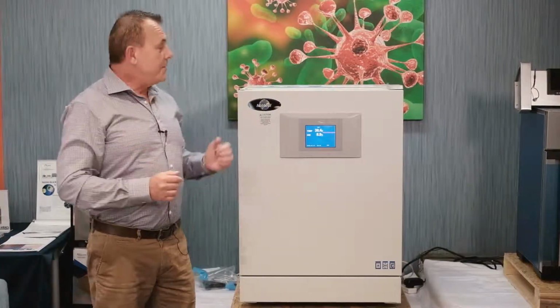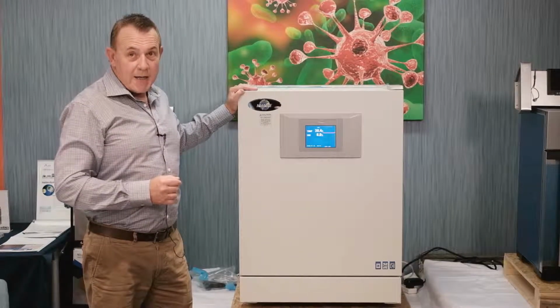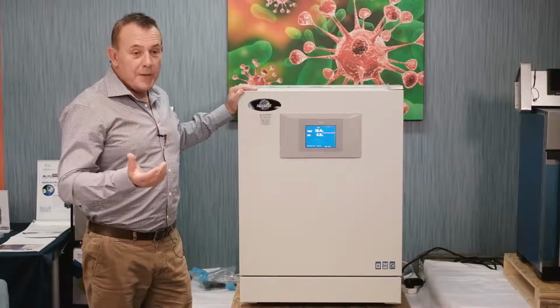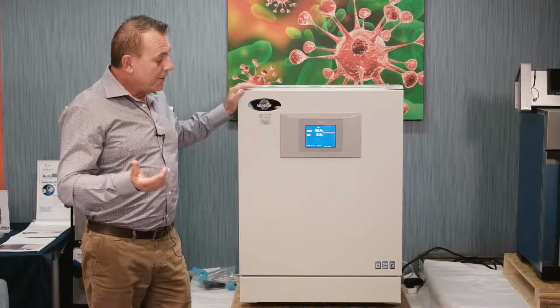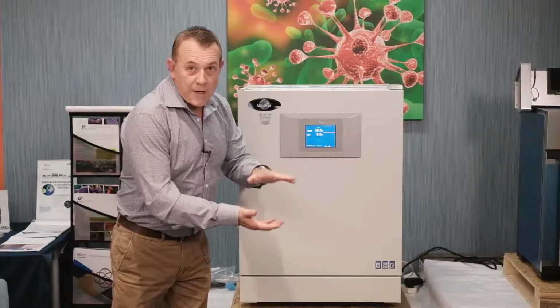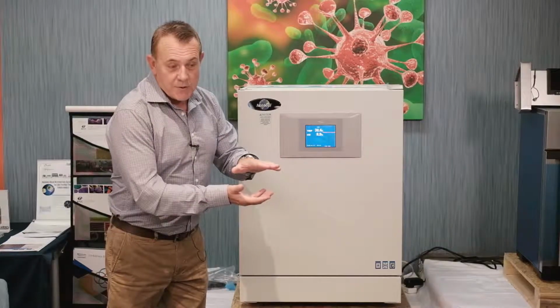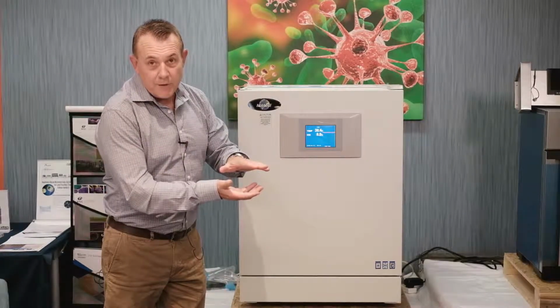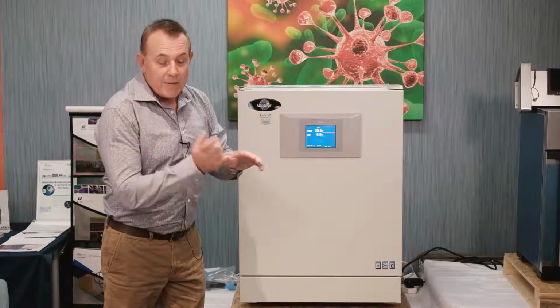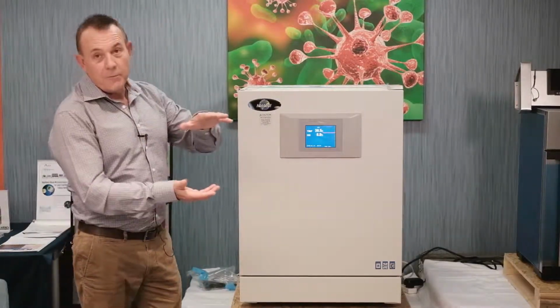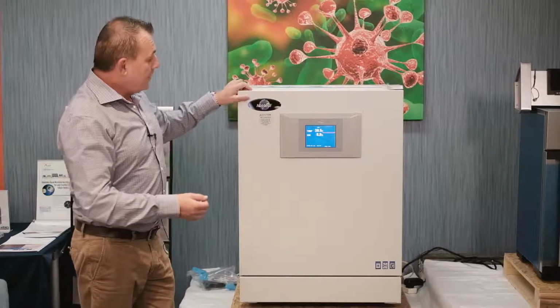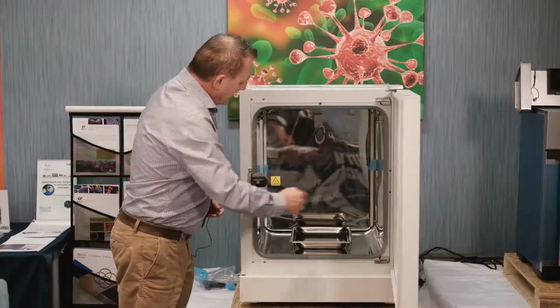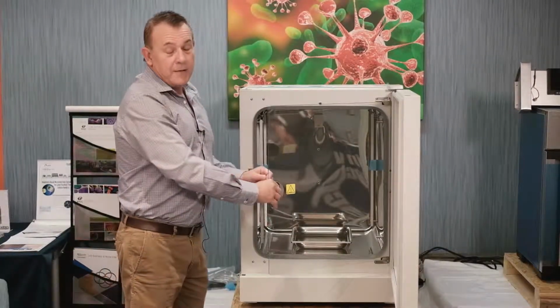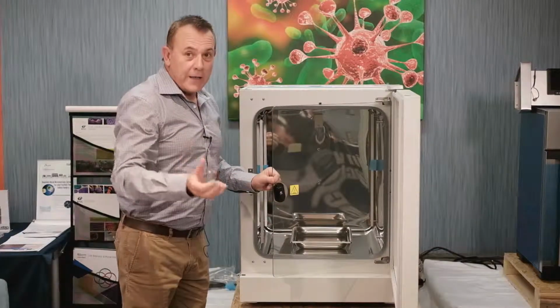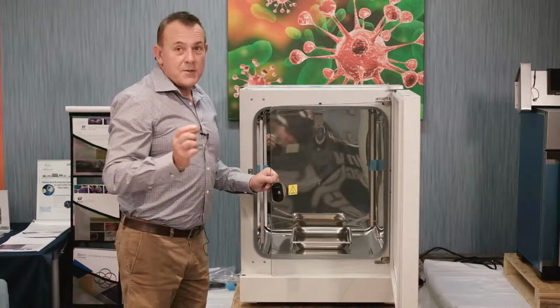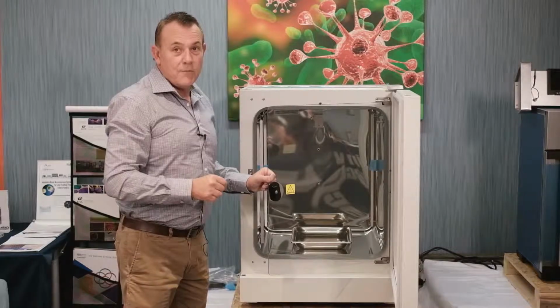Important to note, these NuAire incubators can be stacked, but my recommendation is we also offer a raised platform, approximately 150 mil off the ground. The benefit of raising your incubator off the floor is that when opening and closing the doors, particularly the inner door, you're not creating a draft or vacuum that sucks any potential contaminants off the floor.